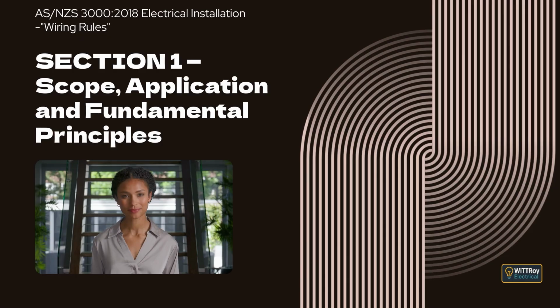Clause 1.5.4.4 Protection by barriers or enclosures. Live parts must be inside something that gives a defined degree of protection. For example, IP2X or IPXXB, meaning a finger cannot reach the live parts. IP4X for horizontal top surfaces people can touch easily. The barrier or enclosure must suit the environment and be strong enough to prevent distortion or damage that could expose live parts. Removal of barriers or covers should not be possible without using a tool or a key, except in controlled conditions. If barriers are removed, interlocking devices or intermediate barriers may be required to automatically keep people away from live parts.